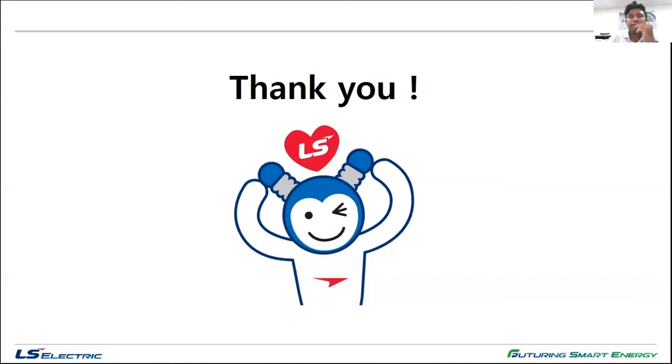Yeah, Mr. Mohammed has asked one question. His question was related to the 3-pole and 4-pole breaker, whether the neutral CT is required or not. Only Mohammed. I've unmuted him. Mr. Mohammed, can you hear me? His question was whether the LS ACB contains ground fault protection. Yes, it's contained. And the question is, if we use the 3-pole ACB, should we add an external CT for neutral or not?